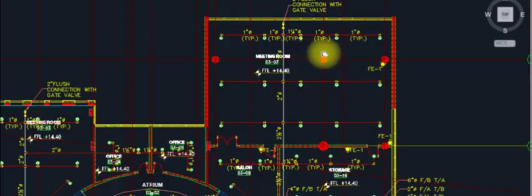This is so simple for calculation. The pipe diameters will be 25, and after that 32, like 1 inch and 1 and 1/4 inch. So this is the criteria. Ordinary hazard is so simple. The sprinkler will cover an area of 130 square feet, or 12.3 square meters.